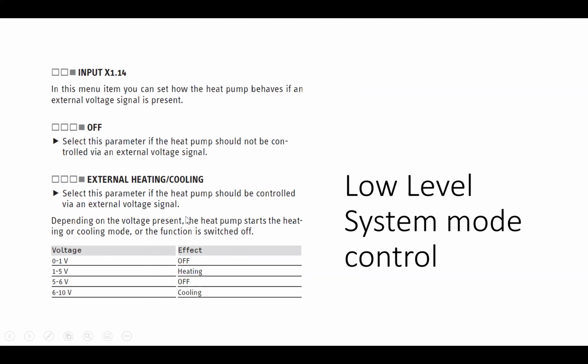It's measuring the weather. Once it gets above a certain temperature for a set amount of time, it switches over onto summer mode. And then we can choose another temperature if we want, or the same temperature, to enable cooling. That is how the system normally will select its mode. However, if we want to force it into a mode, we can via the 0 to 10 volt input. 1 to 5 volts, as you can see, is heating. 6 to 10 volts is cooling.